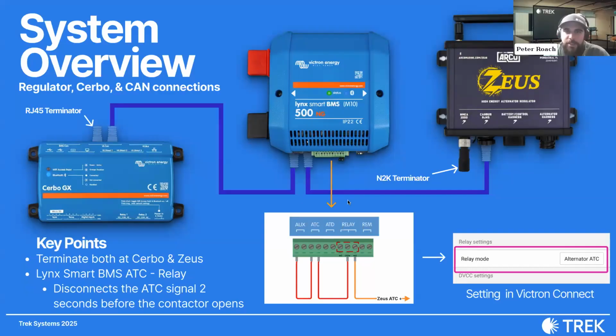One thing I want to highlight with this Lynx Smart BMS, if you look underneath, you'll see this wiring diagram where the ATC output of the Lynx Smart BMS is jumped over to the common of the relay, and from the normally open connection of the relay, that's what connects to the ATC connection on the battery harness. When wired like this, there's one more setting in Victron Connect on the Lynx Smart BMS you need to enable: the relay mode set to alternator ATC.